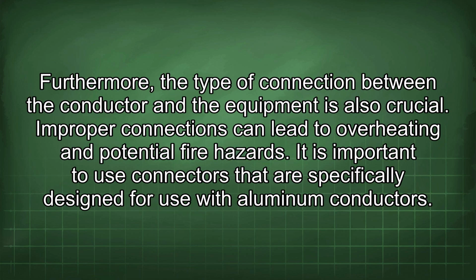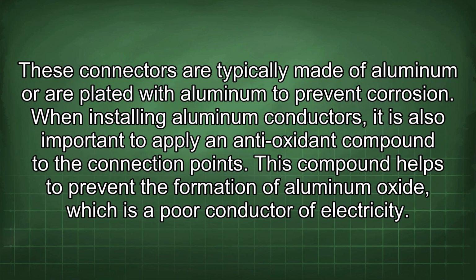Furthermore, the type of connection between the conductor and the equipment is also crucial. Improper connections can lead to overheating and potential fire hazards. It is important to use connectors that are specifically designed for use with aluminum conductors. These connectors are typically made of aluminum or are plated with aluminum to prevent corrosion.